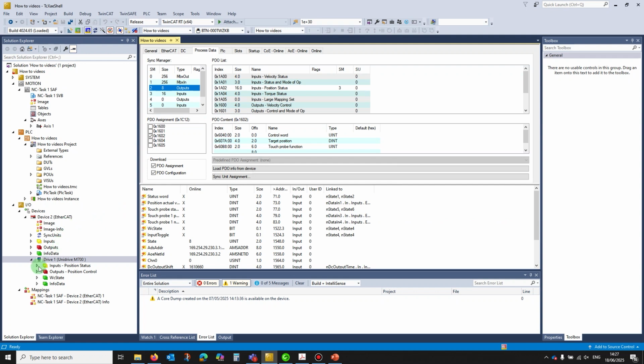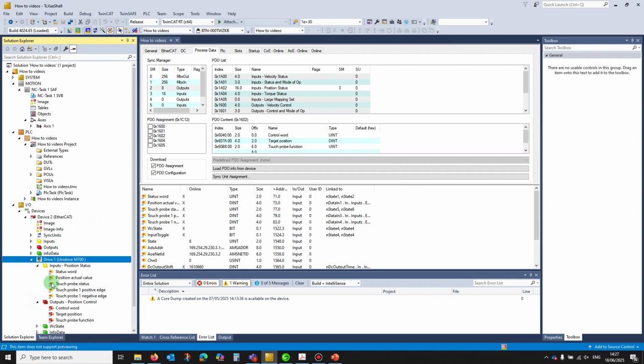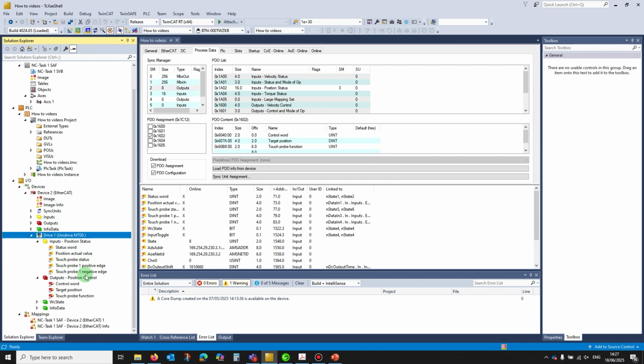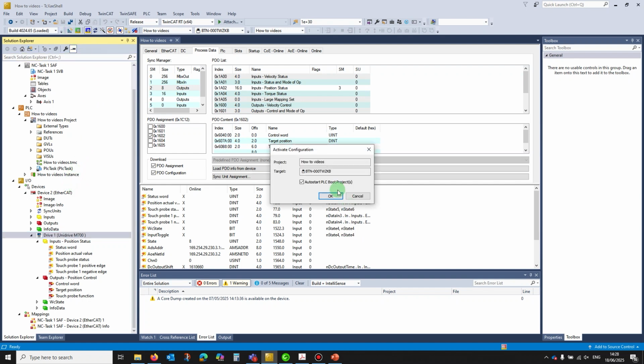Let's have a look at those mappings. If I expand our inputs and outputs, you can see that not only have all our touch probe status, positive edge, negative edge, and touch probe control functionality been added, but this grey box with a little arrow tells us it's been linked to data in our NC axis. So all we've got to do to apply this data, so the touch probe functionality works for the NC axis with blocks like MC Home and MC Touch Probe, is apply the configuration.